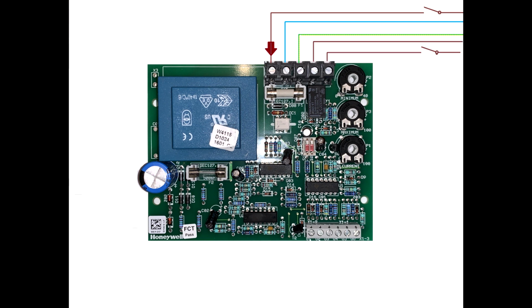Now you have another set of wires just under the power supply, and these wires are meant to bring power to this printed circuit board relay. It's a black relay, as you'll see, where the wires go in, and that relay will close or open the circuit, allowing the signal to be returned to either a burner or a programmable logic control. Underneath the printed circuit board you have two wires which are low voltage that will go straight into these actuators of the gas valve I showed you before.